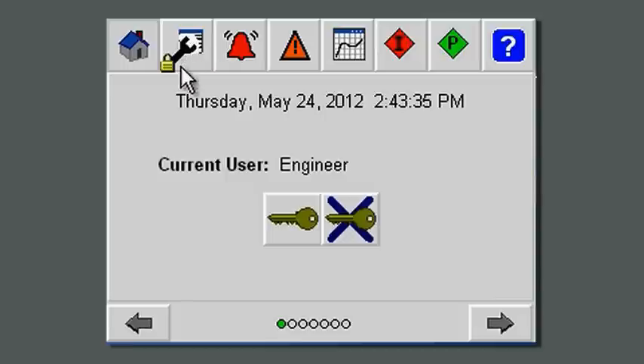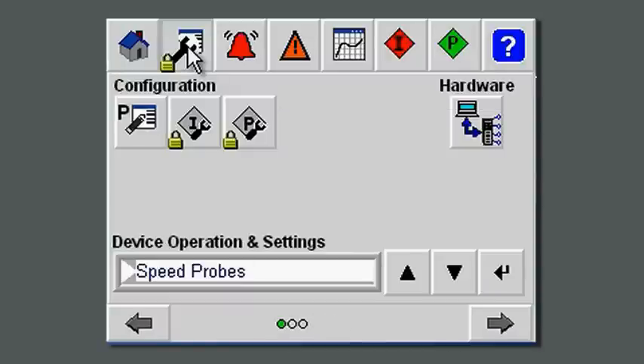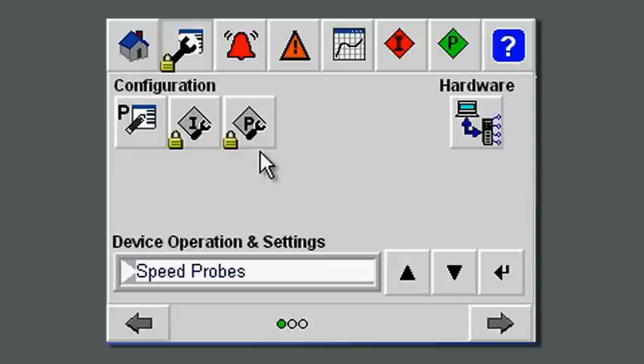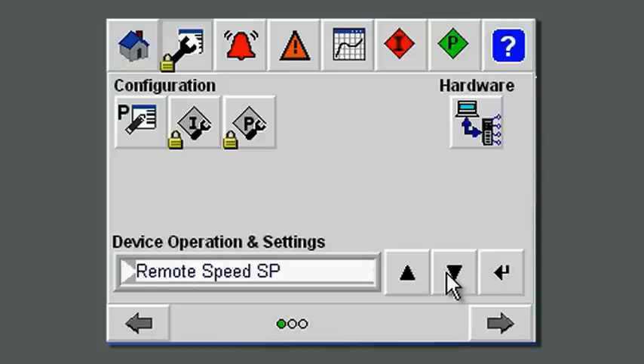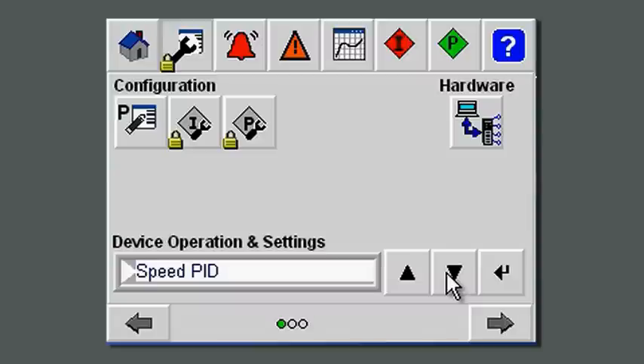If we come up and take a look at the maintenance screens — that's the little wrench you see up here — pressing the wrench brings you up to the configuration, hardware, and device operations and settings page. This particular page allows you to access the configuration parameters, the interlocks, and the permissives. It also lets you look at the hardware diagnostics. The device and settings window lets you choose and look at particular individual items if you're interested in something specific in the configuration.